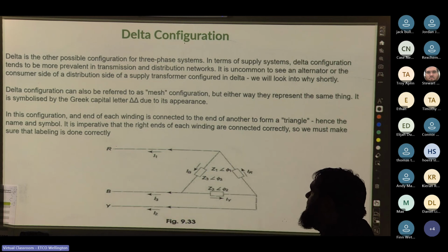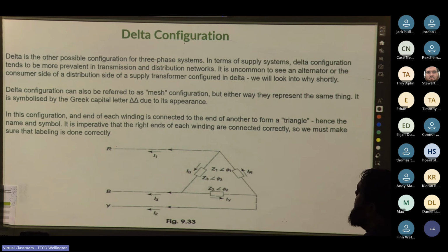Cool. So the other possible configuration you'll come across for three-phase. Delta tends to be more prevalent in transmission and distribution networks on the high voltage side. It is uncommon to see an alternator or the consumer side of a distribution supply configured in delta. The delta configuration can also be referred to as mesh configuration, but either way, they represent the same thing, symbolized by the Greek letter. And we've talked about the way they're connected to form a triangle.